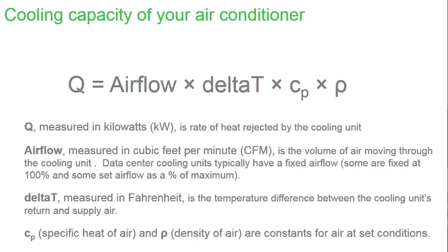Q, measured in kilowatts, is the rate of heat rejected by the cooling unit, and this represents the heat from your IT equipment. Then we have the airflow, measured in cubic feet per minute — sometimes you hear people call it CFM — and this is the volume of air moving through the cooling unit. Delta T, measured in Fahrenheit, is the temperature difference between the cooling unit's return and supply air. Finally, we have CP, the specific heat of air, and rho, the density of air — these are constants for air at set conditions.